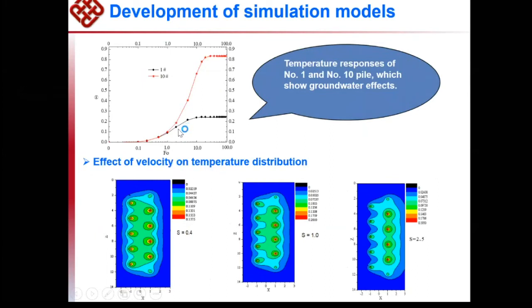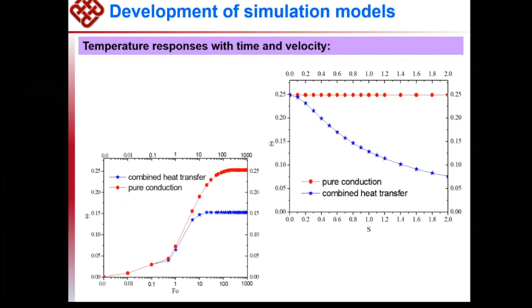You can see on the chart, this is a dimensionless temperature difference of the ground. For the temperature response in the ground soil, the red curve represents number 10 borehole pile temperature response, very high temperature, and the black one represents number one. This is because water flows from the left hand side. So the conclusion is that water advection effect must be considered for simulation analysis of the ground pile ground heat exchanger, not just pile.